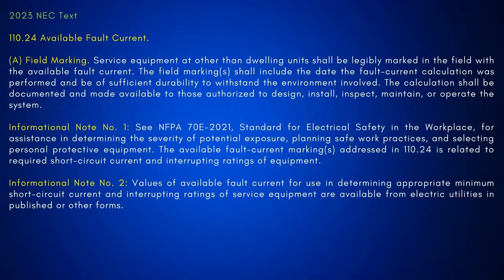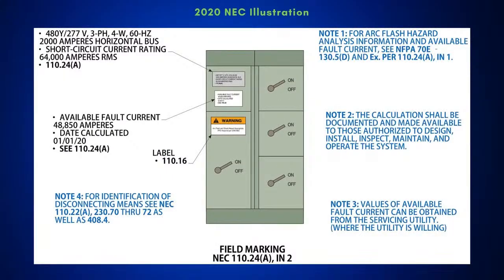And then you drop down and you pick up Informational Note number 1. And what does it tell you to comply with? NFPA 70E, the 2021 version, for electrical safety in the workplace. And this is to help with determining what? The severity of potential exposure, planning safe work practices, and selecting your PPE. You remember the course we did a couple weeks back, where I showed the difference between the table and the calculation method. This is another portion that would go with that. So you would have to look at that and understand it.